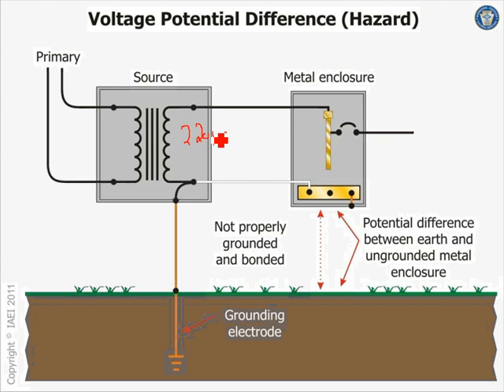So here's your 220. On this side, what is it? 6.6 kV. They bring between 2 phases. So your transformer is coming out of 6.6. That's the voltage that they use. 6.6 kV phase to phase voltages. 220 here. Again, you're bringing your neutral, the utility grounding their transformer here, and you are not to ground the neutral again here. But what we do actually, you have to create a ground here though. You have to create your ground, but what you don't do is you don't bond this. So this does not exist.